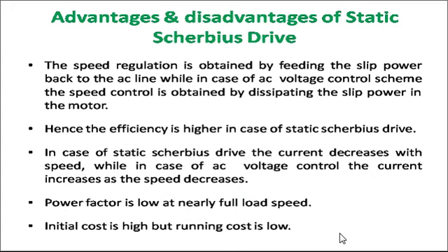Further, we can see the advantages and disadvantages of the static Scherbius drive. As we have already discussed, the slip power is fed back to the AC line, so the efficiency of this system is higher as compared to the voltage control scheme.